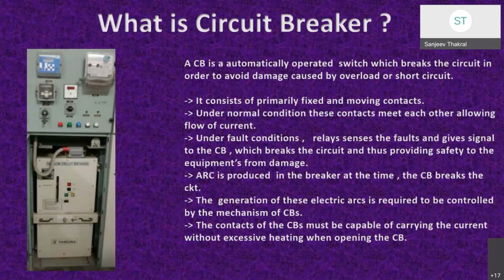It consists of two parts, a moving one and a fixed one. Under normal conditions, these contacts meet each other, allowing flow of current, and will not open until and unless the circuit becomes faulty. Under fault conditions, the relay senses the fault and gives a signal to the circuit breaker. The tripping coil of the circuit breaker gets energized, which breaks the circuit and thus provides safety to the equipment from damage. An electric arc is produced in the breaker at the time the circuit breaker breaks the circuit.